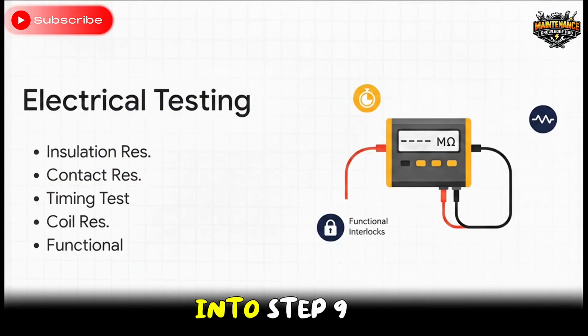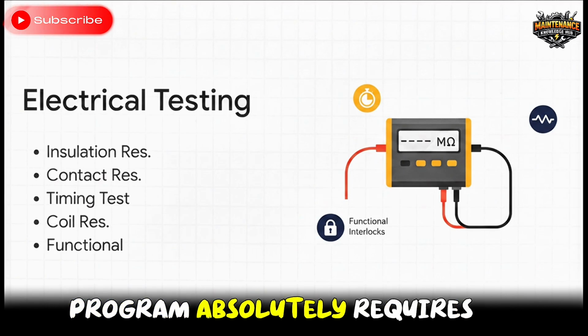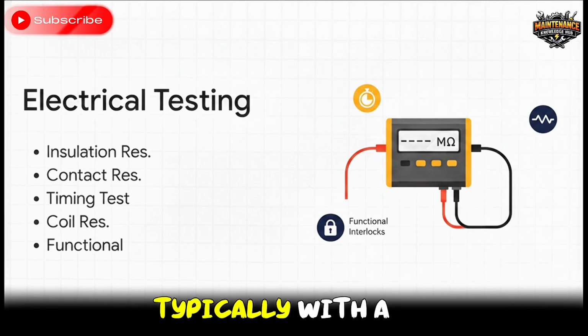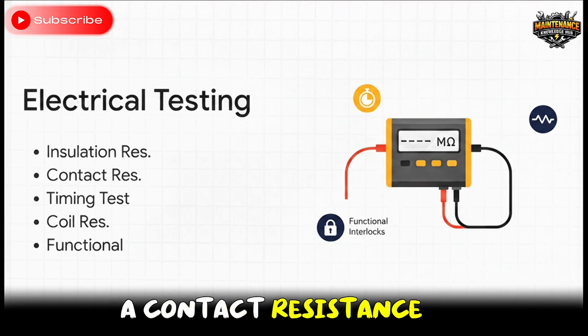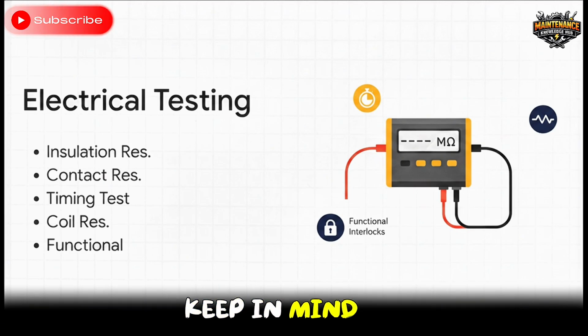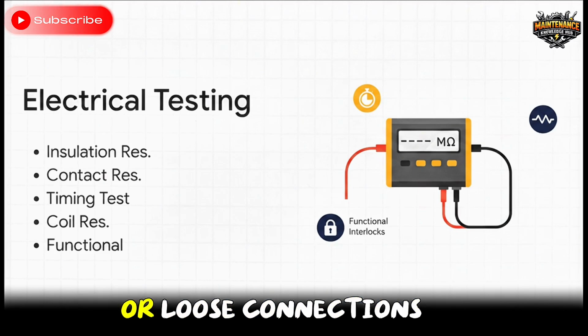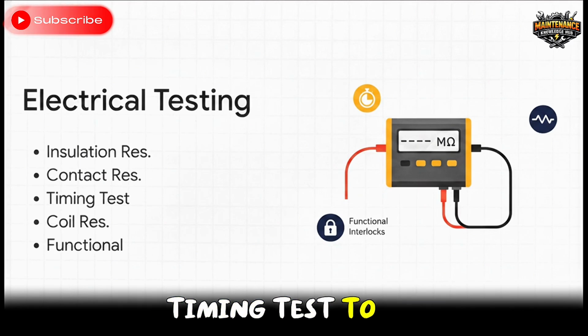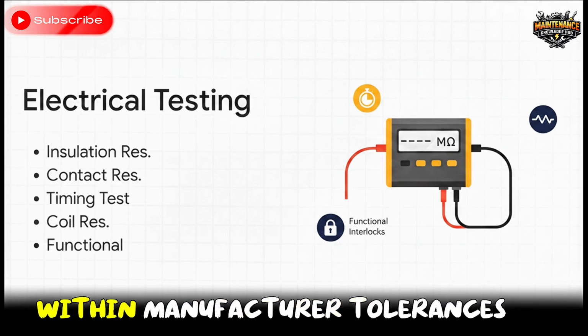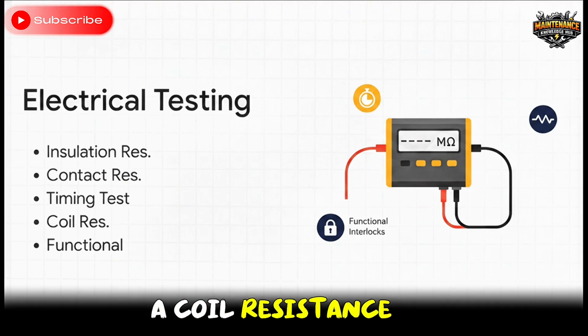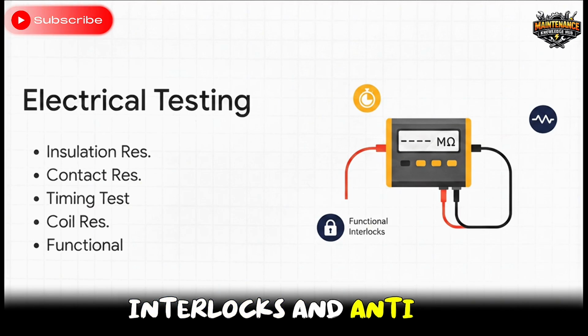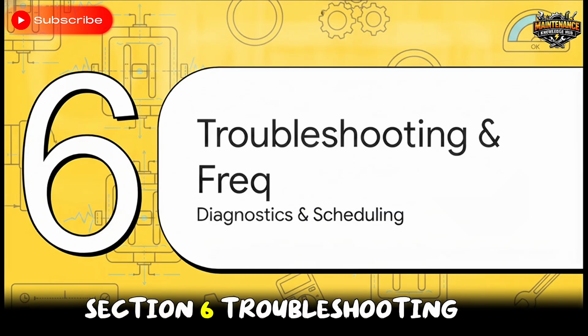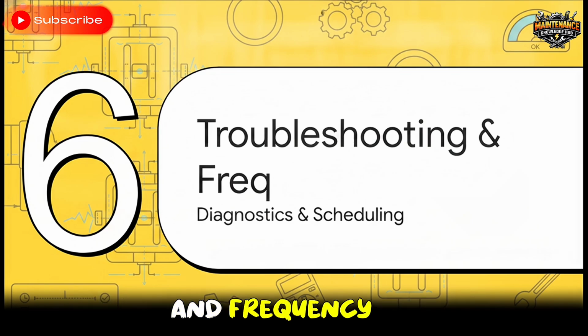Let's do a quick deep dive into step 9, the electrical testing, because it's so important. A proper maintenance program absolutely requires measuring insulation resistance, typically with a megohmmeter. You also need a contact resistance test using a micro-ohmmeter. Keep in mind, high contact resistance is a massive red flag. It almost always indicates worn contacts or loose connections. You're also going to run a timing test to verify those opening and closing speeds are strictly within manufacturer tolerances, plus a coil resistance test for your trip and closing coils, and a functional verification of all your safety interlocks and anti-pumping features. Section 6, Troubleshooting and Frequency.